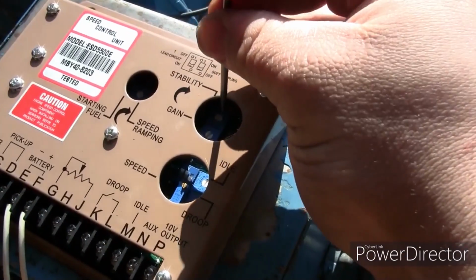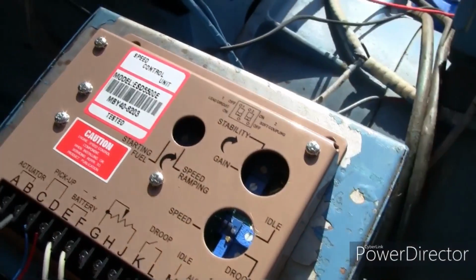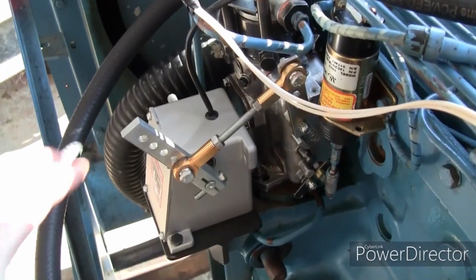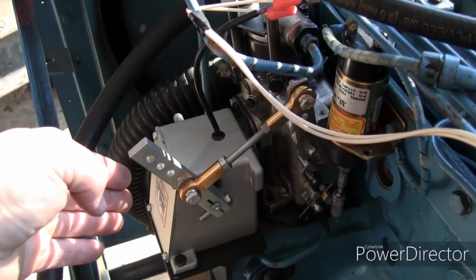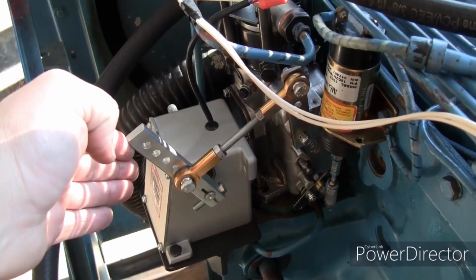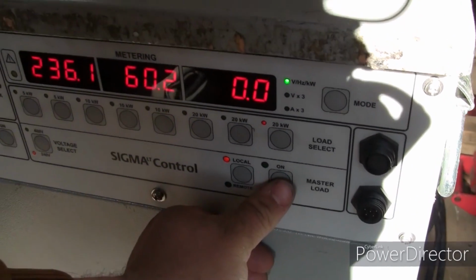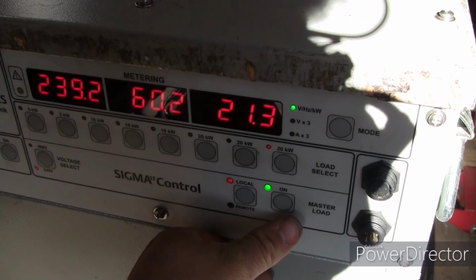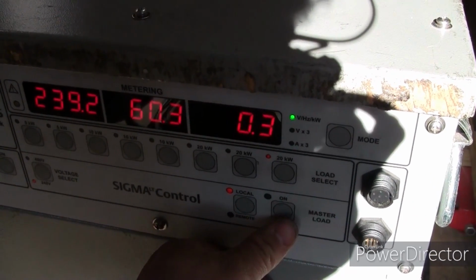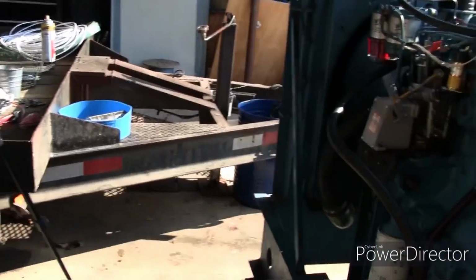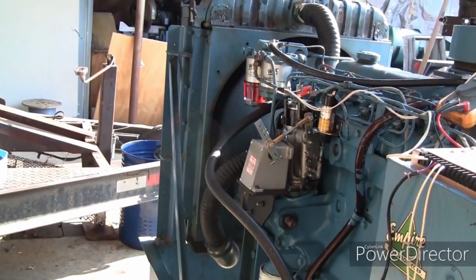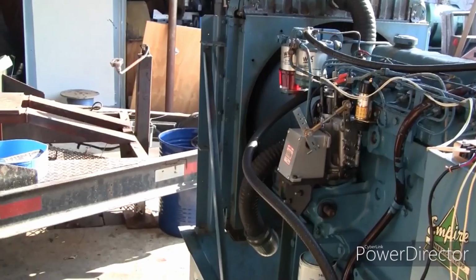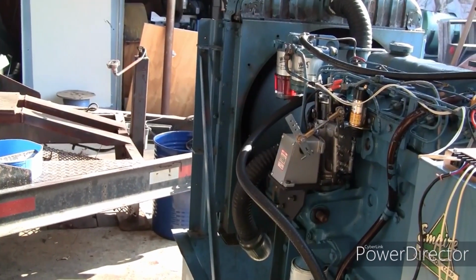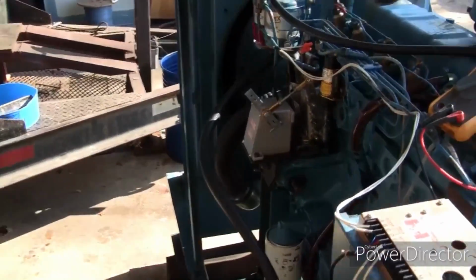Let's see if we can improve it a little bit more. A little less overshoot. That's a bit better. Yeah, so with about a 50% load, it looks like we only have maybe half a cycle of variation there. Like, it doesn't even get out of the 60 hertz cycle. Not bad. I mean, it's night and day compared to the mechanical governor.